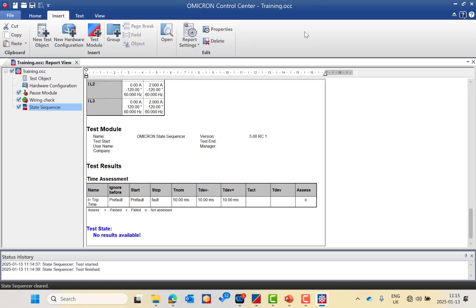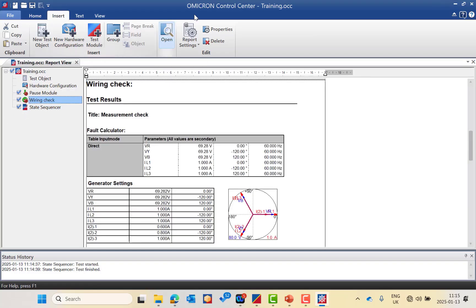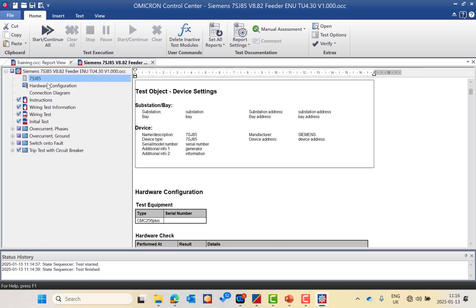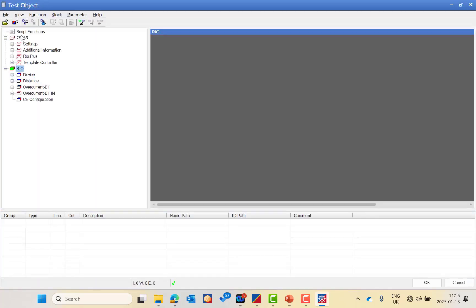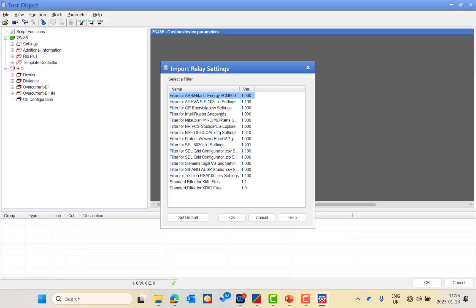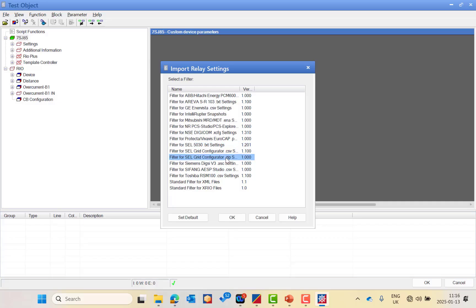This is the state sequencer module. I will now go back to the PTL — the Siemens 7SJ85 PTL available on our customer portal. To import relay settings, press File and choose 'Import Relay Setting'. Different import filters are available based on relay type and manufacturer: use the standard XRIO filter for Siemens, the TXT file for SEL relays, the csv file for GE, and many more filters for other protection relay types.